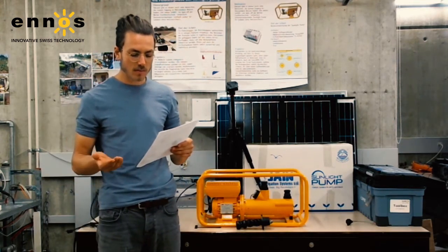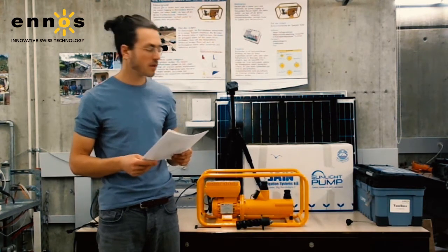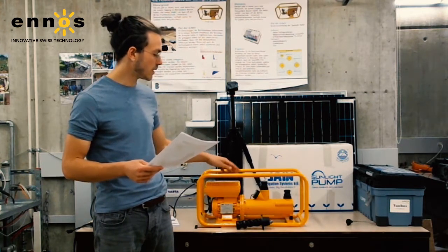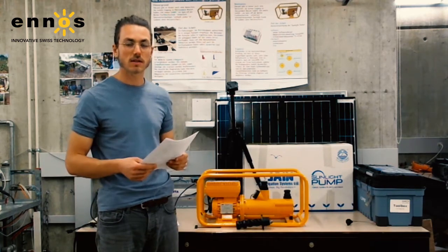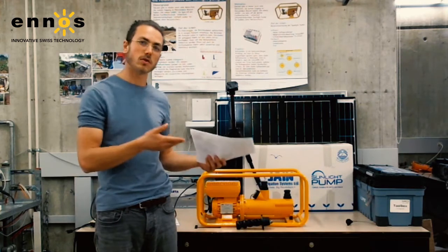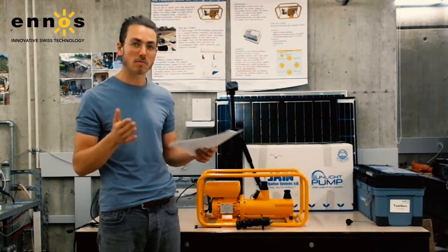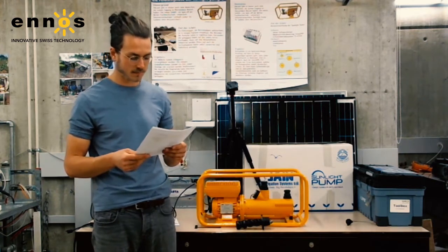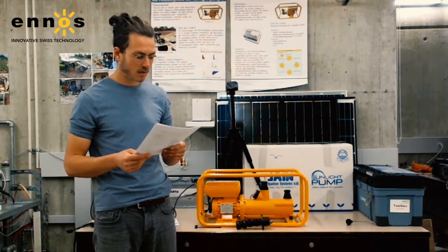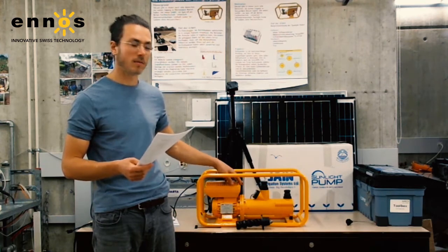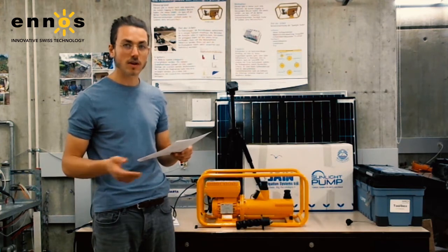Then you've got the operation temperature of the pump, which is 0 to 50 degrees. That's the recommended industry standard for pumps like this. Same goes for the temperature of the storage. Again, this is an industry standard, and make sure to use your pump and store your pump at these levels. So storage would be between -30 and +55 degrees. Pump dimensions, you can see for yourself, quite compact for the power that it delivers. The weight is at 14 kilograms, which makes it portable.